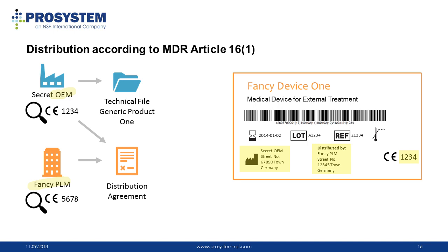Like I said, you've got the description of the requirements in Article 16 for these distributors, and so everything is written down there. So if there is the possibility that you can write the original manufacturer on your product, and your original manufacturer is willing to fulfill all these requirements and has the capabilities to fulfill all these new MDR requirements, this is a solution, of course, that you can choose.